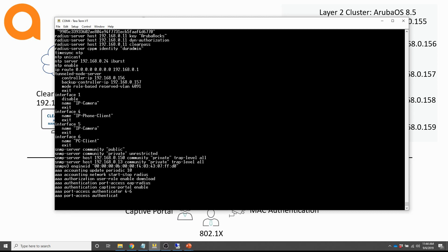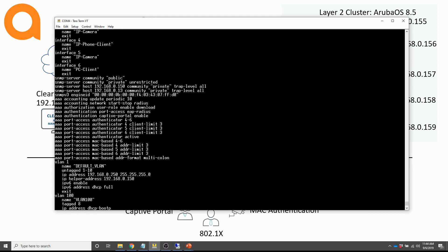Let me start with the switches. On the switch you have to configure SNMP. I'll just be using straightforward SNMP v1 or v2, but any SNMP version will do the trick. Since it's for monitoring purposes only, it doesn't really matter whether you configure a read-only or read-write community. Let me show you the configuration for SNMP — really very straightforward.